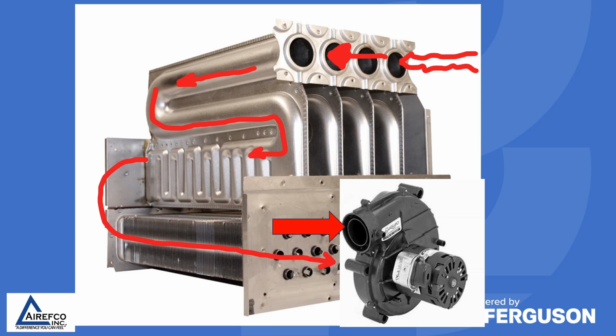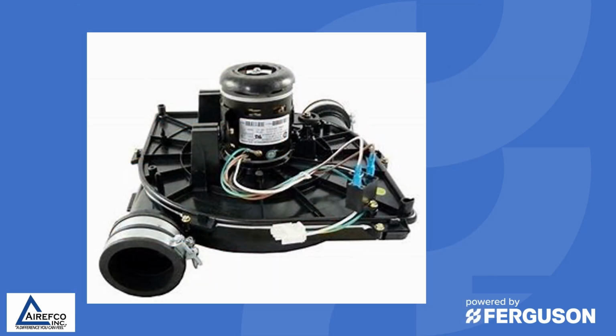You'll also notice that most of your inducers have an inner tube and an outer tube. The inner tube is directing the vent gases into the vent to the outside, while the outer tube collects the moisture or the condensation that is made by the secondary heat exchanger and directs it to the condensate trap. So the inducer motor is generally attached to a plastic blower housing that is designed to channel the vent gases into the vent and the condensate into the condensate trap.